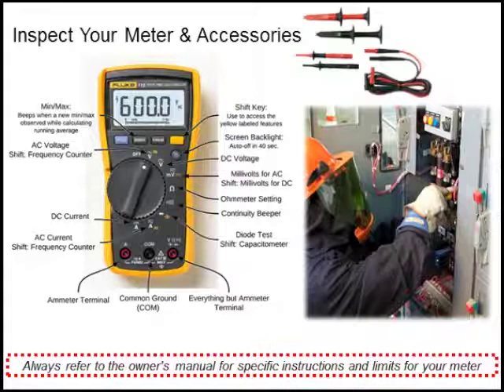If your meter passes inspection, you've got to verify that your meter is functioning properly. We call this a live, dead, live process. In other words, we're going to go to a known source and test our meter, if we're testing voltage, in the same range of voltage that we want to perform on our equipment. If the meter works properly, then we can go out and do our tests. When we're finished with that testing, we go back to our known source to assure that the meter is still working properly, because you could have damaged that meter in the previous testing. Again, that's called live, dead, live testing.